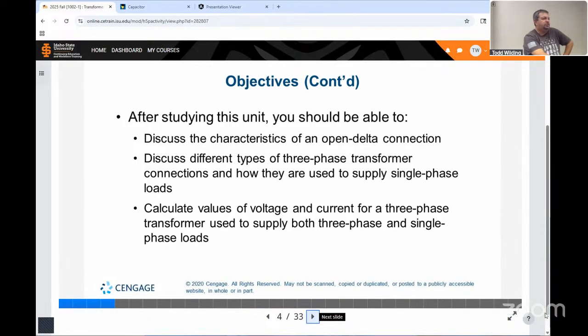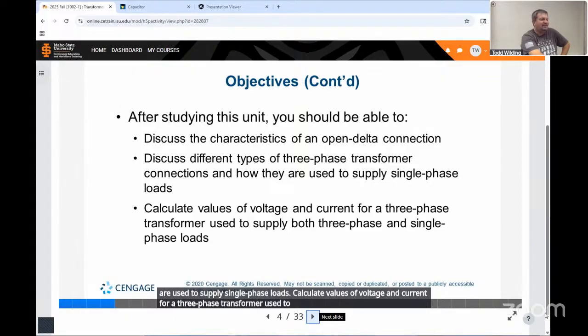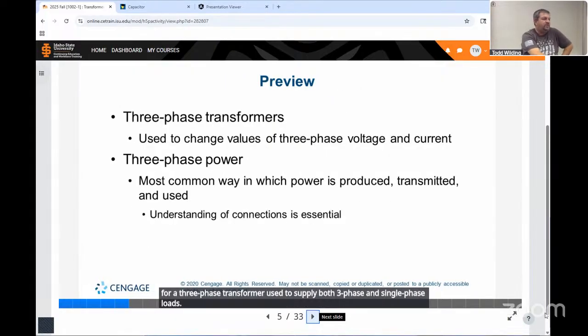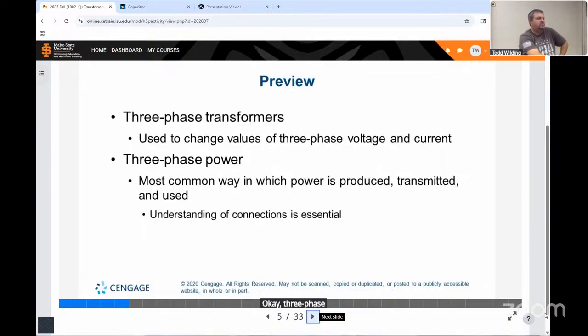After studying this unit, you should be able to discuss the characteristics of an open delta connection, discuss different types of three-phase transformer connections and how they are used to supply single-phase loads, and calculate values of voltage and current for a three-phase transformer used to supply both three-phase and single-phase loads. Okay, three-phase transformers are used to change values of three-phase voltage and current. Three-phase power is the most common way in which power is produced, transmitted, and used.